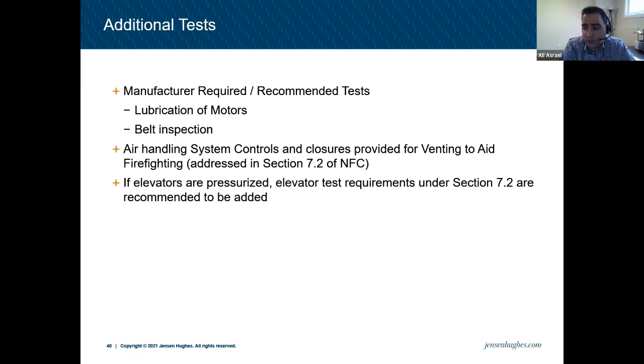And if the elevators are pressurized, the other test requirements under 7.2 that are for elevators, we add them too. Because again, you're bringing in an elevator technician on site to do this test, so might as well do the other test and document it in one document. If it's not a pressurized elevator, that's fine, like a measure A. I understand that. But something like the air handling system, your exhaust system in the parking, to me, should be included. Excuse me.